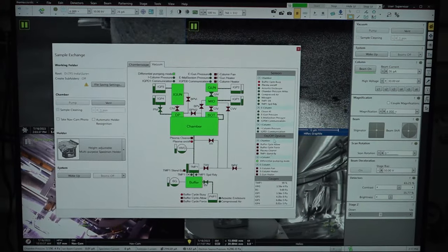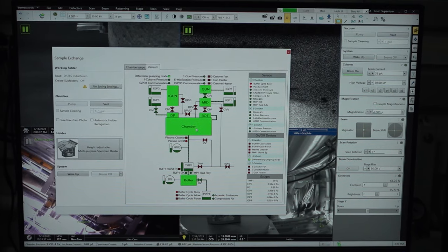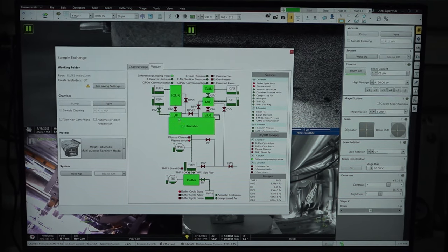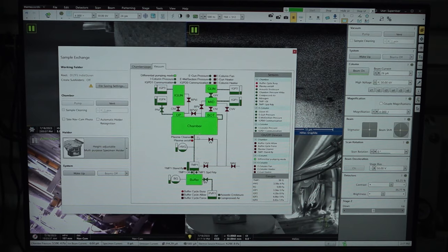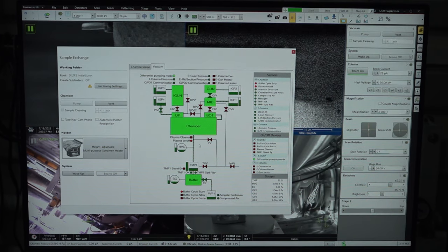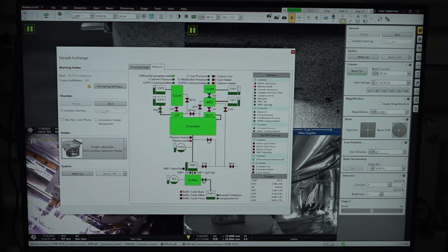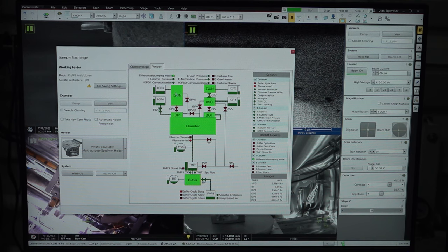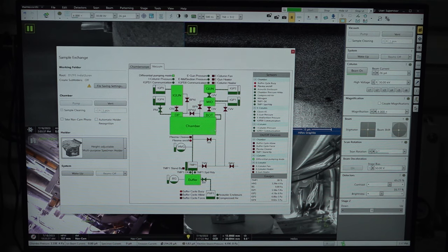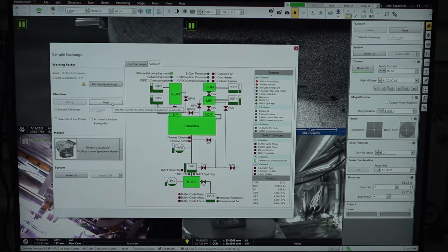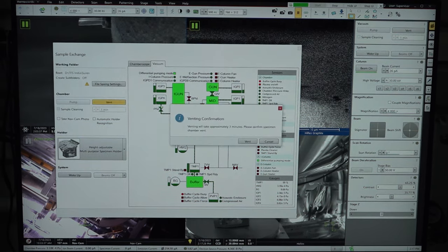This is the vacuum page window. Here you can see there are two differential pumping systems — this is the chamber vacuum and this is the column vacuum. Since there are two columns, it is a dual column system which has an ion gun as well as the electron gun. First we will load the sample by venting the chamber. Let us vent the chamber now.